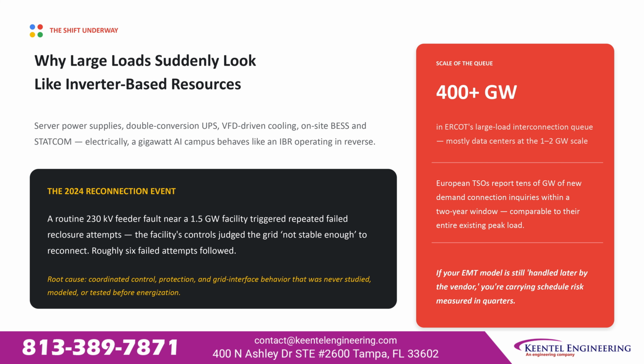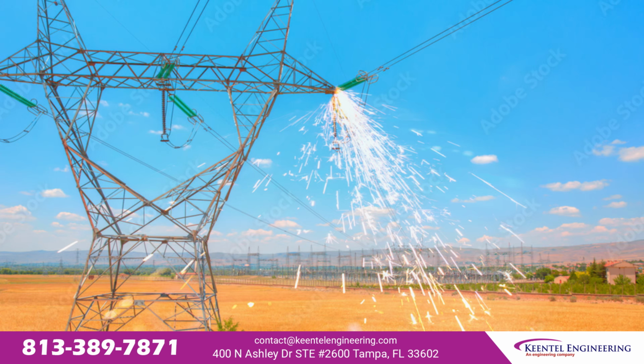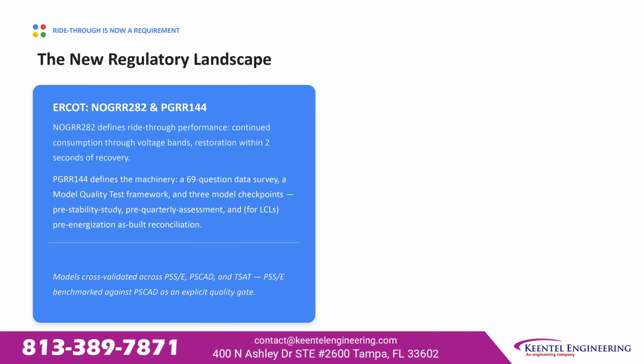Over 400 gigawatts now sit in ERCOT's large load interconnection queue, mostly data centers at the 1 to 2 gigawatt scale. European TSOs report tens of gigawatts of new demand connection inquiries within a 2-year window, comparable to their entire existing peak load. If your EMT model is still handled later by the vendor, you're carrying schedule risk measured in quarters. In ERCOT, 2 rules define the machinery.